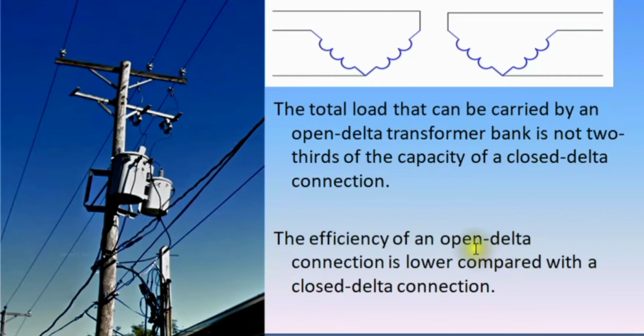The efficiency of an open delta connection is lower compared with a closed delta connection, because the transformers will be operating at a different condition. At full load, both transformers will operate at rated capacity, but their efficiency will be lower since their losses will be at full load losses, so their output will be reduced. But of course, we could still use open delta but at a reduced efficiency. It will tend to cause the transformers to increase in temperature compared to when used in closed delta connection.